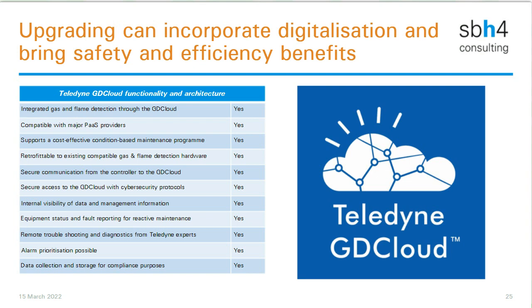And some of the intelligent workings within the cloud-based systems can be, for example, alarm prioritization. Absolutely critical. If we have a relatively complex refinery and perhaps multiple alarms going off at any one time, if I've got 3 or 4 alarms going off, 2 or 3 may be quite trivial in comparison to the other 2. Or there may be one alarm that is incredibly important. And if it's getting lost in a noise of 3 or 4 other alarms, then that could be quite a problem. So using significant data management facilities and interpretation of the data to give really important safety information, alarm prioritization, these are all some of the benefits that can be achieved with significant data management systems such as the GD Cloud.